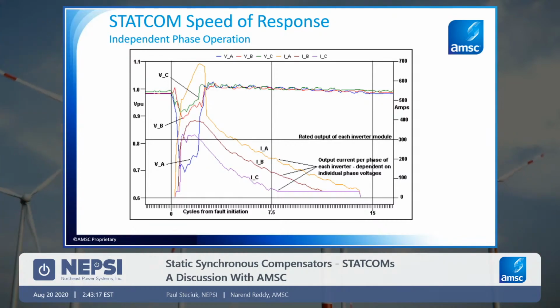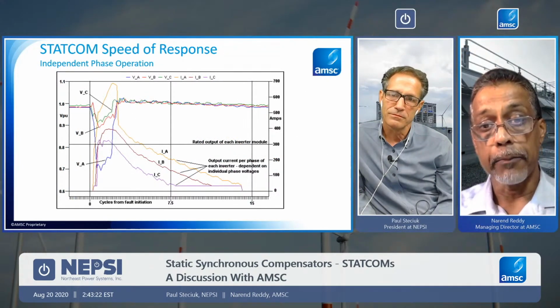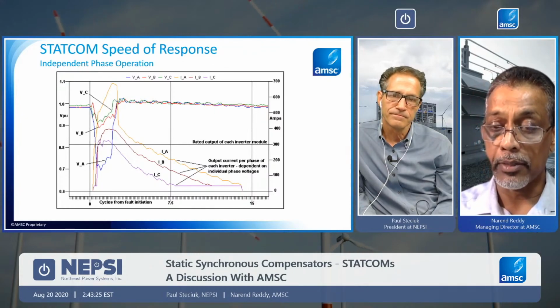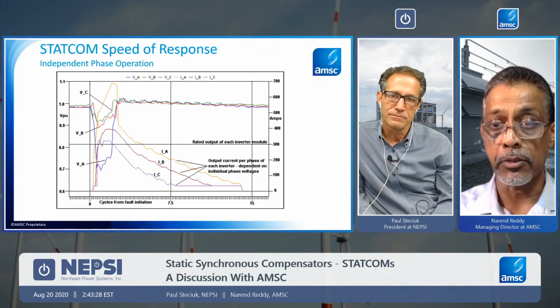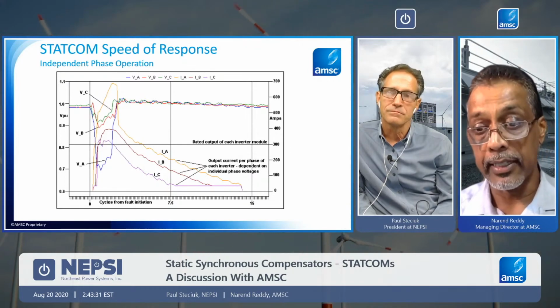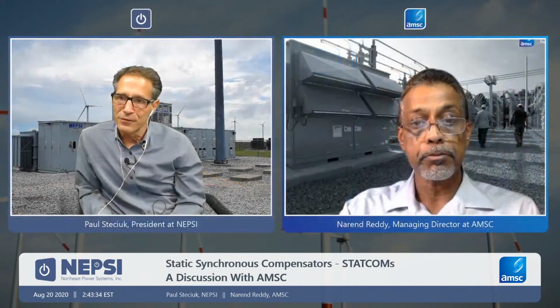Almost all the event here happened in less than about 14 cycles from fault initiation and over. But that's the design concept, and that's the application concept of a STATCOM: how fast it comes in, solves the problem, and gets out of the way. So that's very interesting, and when you talk about droop and response, these are terms that you often hear when you talk about generators and excitation systems. So you are crossing into that same area of what an exciter does inside a generator, or the exciter does in a synchronous condenser.